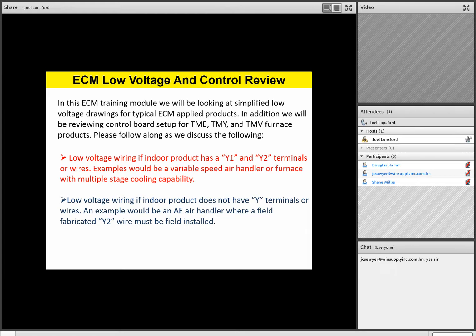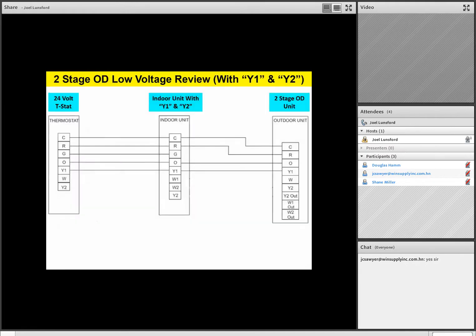So the first thing I'd like to talk about is oftentimes we see our two-stage cooling, two-stage heating products hooked up with an outdoor unit that has two-stage capability. And some examples would be like our AL or HL19 product, which would be a two-stage product. We also have a two-stage 17 SEER product, like our TH17, which is also a two-stage product. It has a two-step scroll compressor out there.